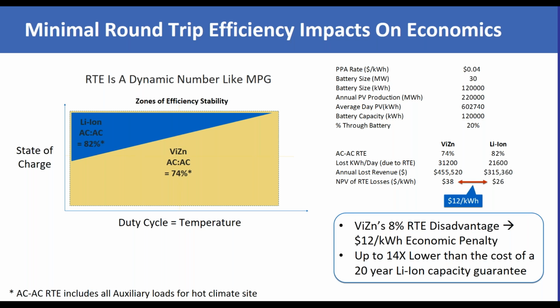And when we talk round trip efficiency, we mean AC round trip efficiency, including all auxiliary loads, right? And it's actually one of the most frustrating pieces of specsmanship that I'm seeing across battery vendors, because folks aren't being straight about what to expect from complete system performance. They're either not including auxiliary loads or not including losses in the inverter, so they're running around talking about round trip efficiencies in the 90% range.